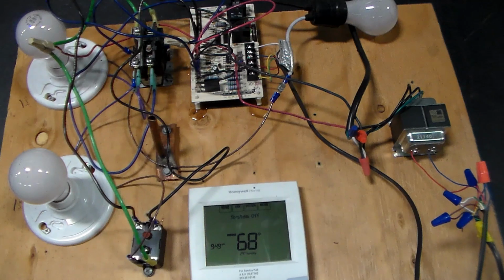Let me start by zooming in on this defrost board. Even though it looks like a rat's nest of wires, they're all the same, and they all wire relatively about the same. This one is a newer style, so it has the capability of having the high and low pressure sensors in your system, which I have bypassed here, but some of the more basic defrost boards don't have that. They're even more basic, which we'll look at a few different styles here in a little bit. But first, we need to get familiar with the basic operation of a heat pump and how the board is wired. Generally, they're all about the same. Once you understand it, then really you understand them all. So let's get zoomed in on that board so we can talk about that first.